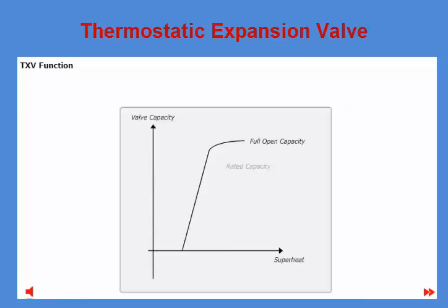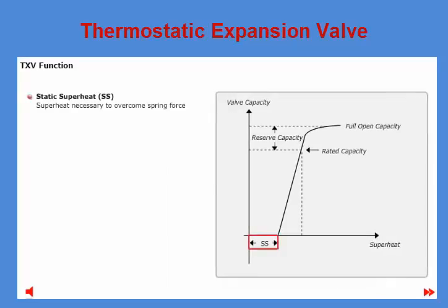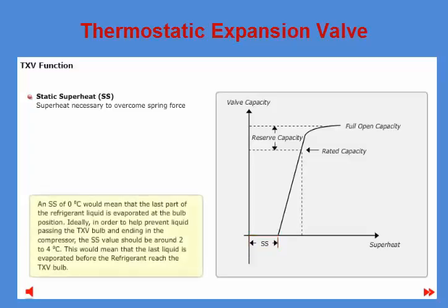Superheat in relation to the TXV function is a combination of two values or parts. The first part is called static superheat, or SS — the number of degrees of superheat needed for the valve to overcome the closing force from the TXV mainspring. SS is measured at the TXV bulb position. An SS of 0 degrees would mean that the last part of the refrigerant liquid is evaporated at the bulb position. Ideally, to help prevent liquid passing the TXV bulb and entering the compressor, the SS value should be around 2 to 4 degrees.